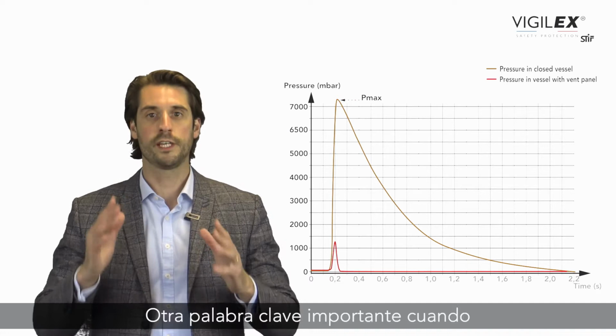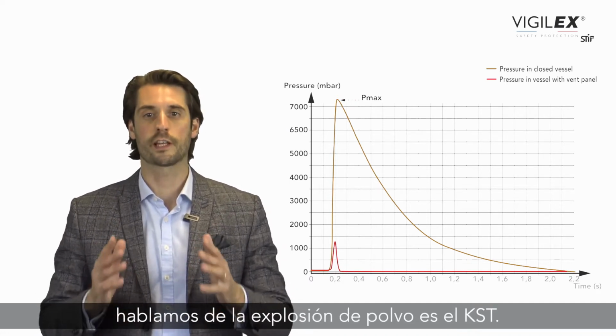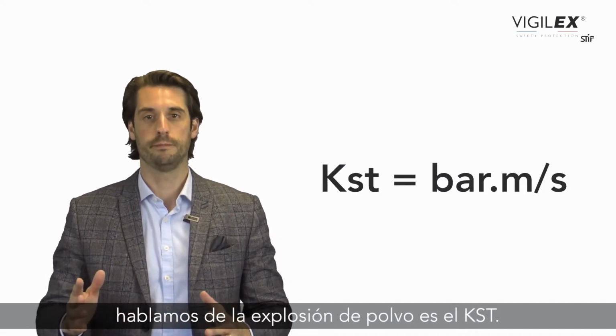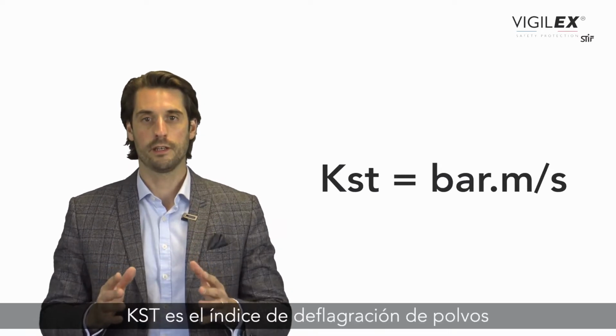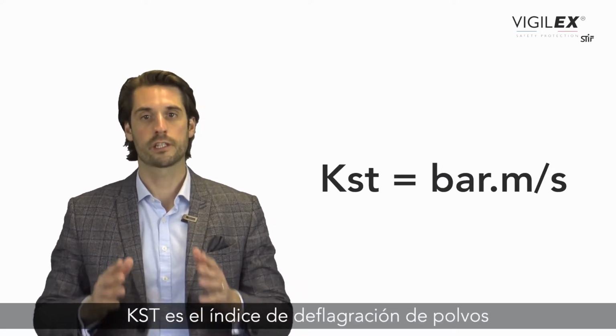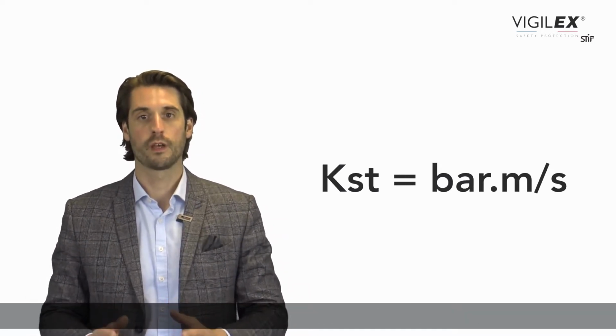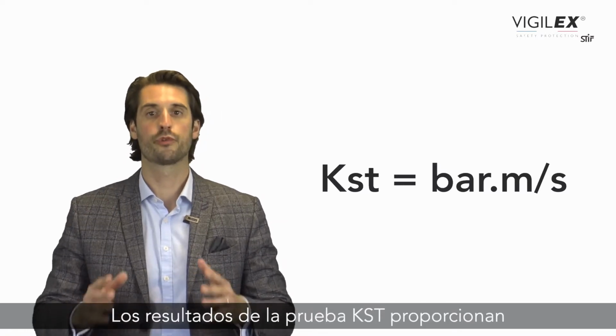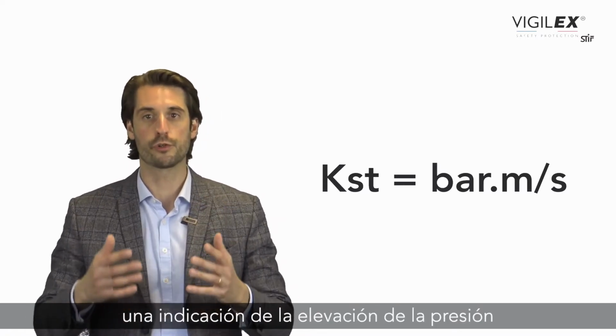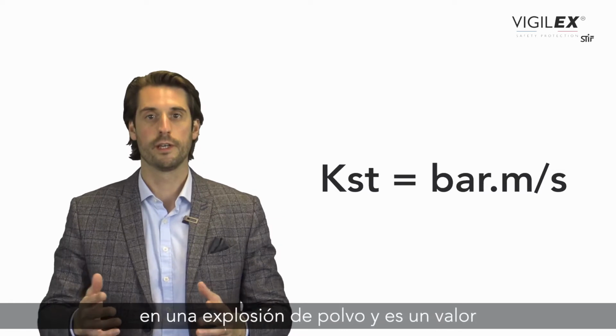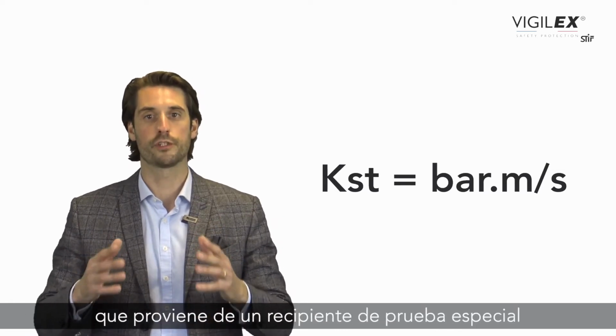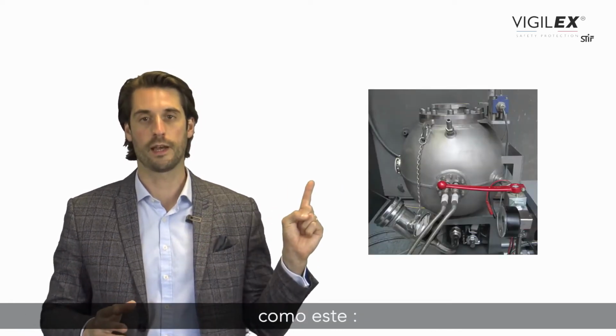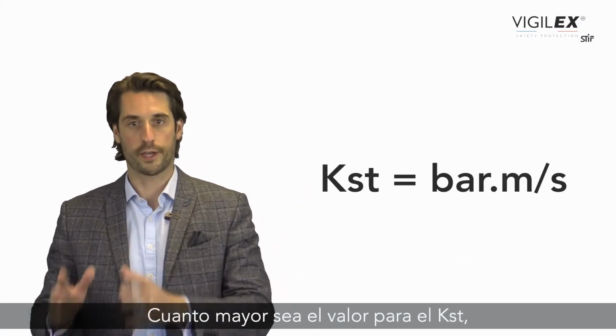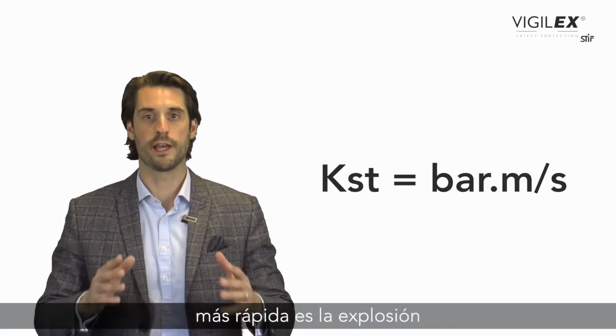Another important keyword when we talk about dust explosion is the KST. KST is the deflagration index for dust. The KST test results provide an indication of the pressure rise in a dust explosion, and it is a value which comes from a special test vessel, like this. The larger the value for KST, the faster the explosion.